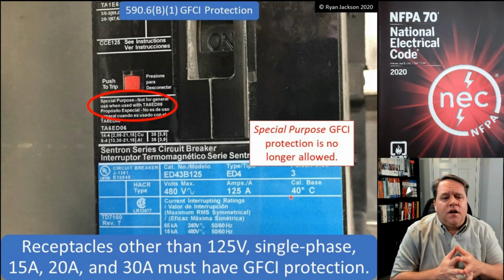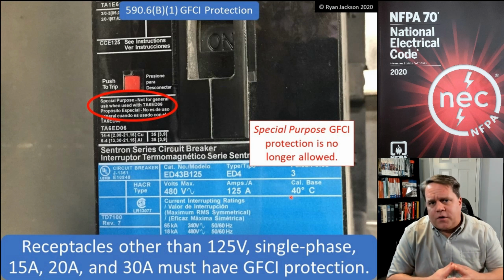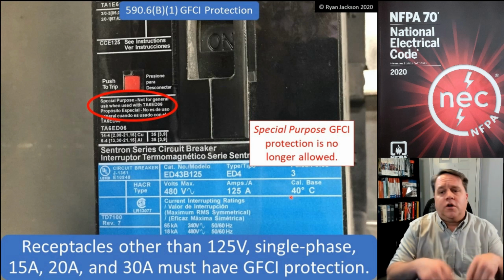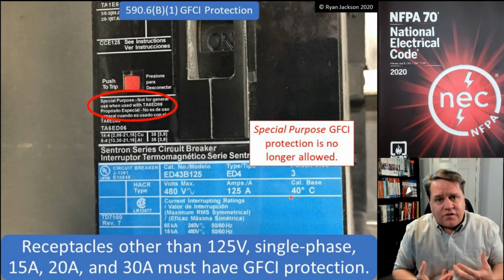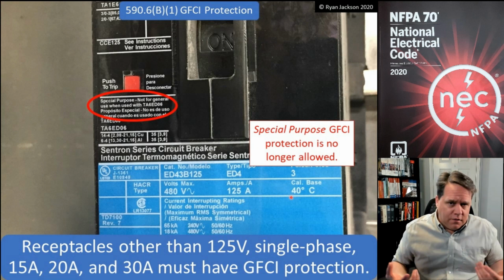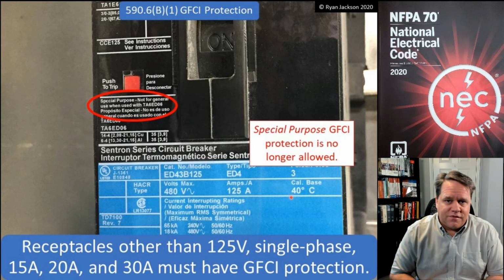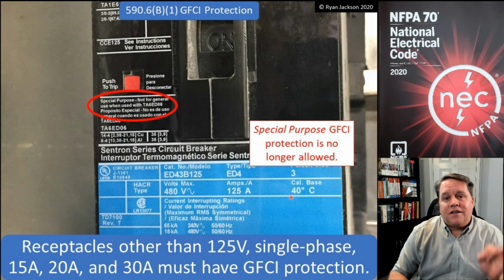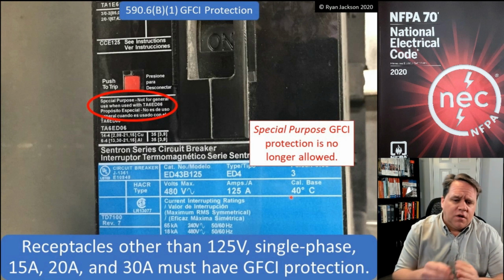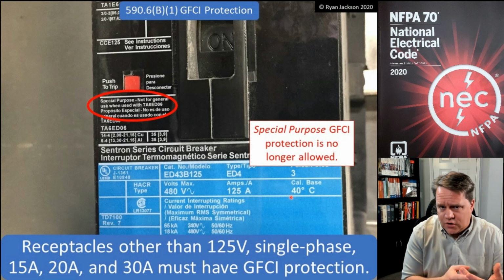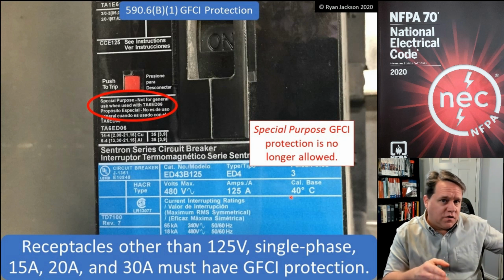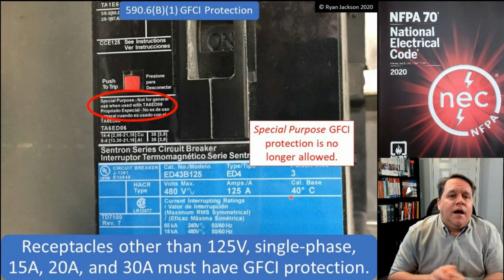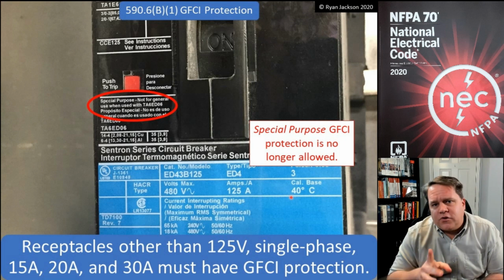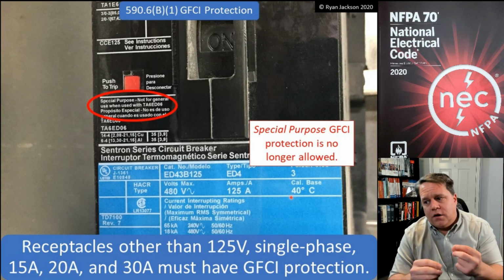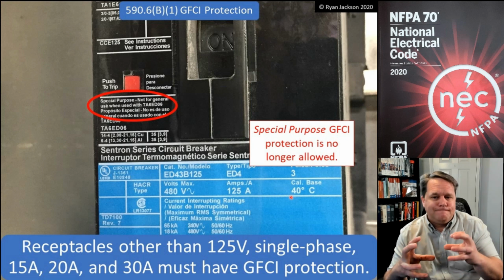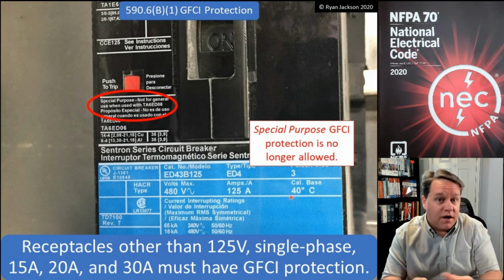So special purpose GFCI protection is GFCI protection that falls outside of the boundaries of what we call Class A GFCI. And anytime in the NEC we have a GFCI rule, it has to be a Class A device, because that's part of the definition of GFCI. And a Class A device means that it opens at currents greater than 4 to 6 milliamps of leakage current. So it will stay closed at leakage currents less than 4 milliamps, and it will open at leakage currents of more than 6 milliamps. A special purpose GFCI can trip at other ranges, and the voltage is different, and also the response time can be different as well.